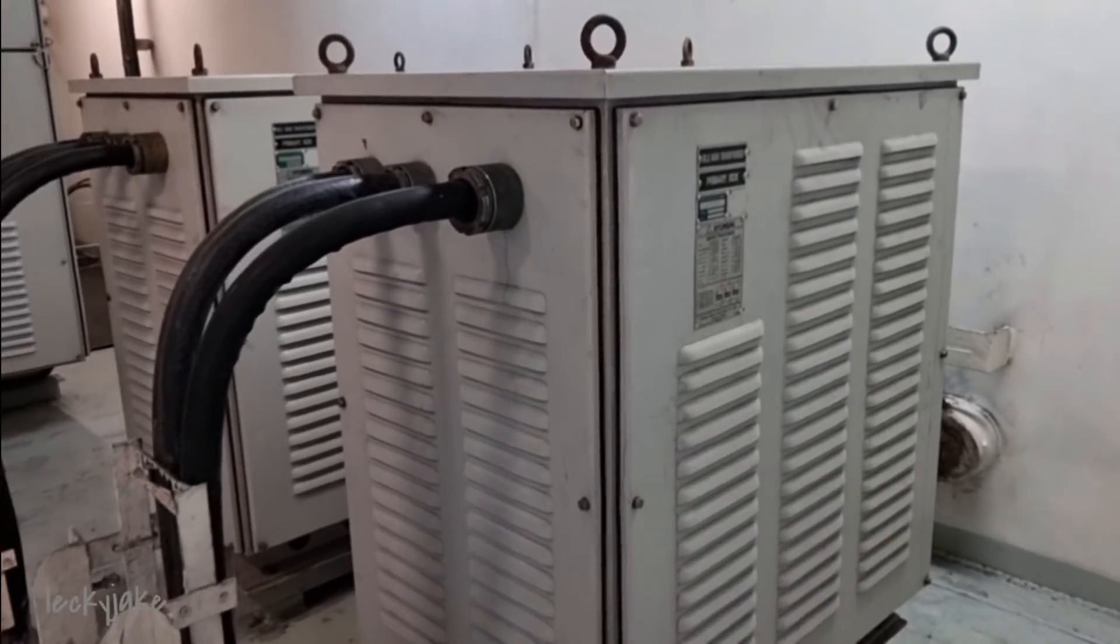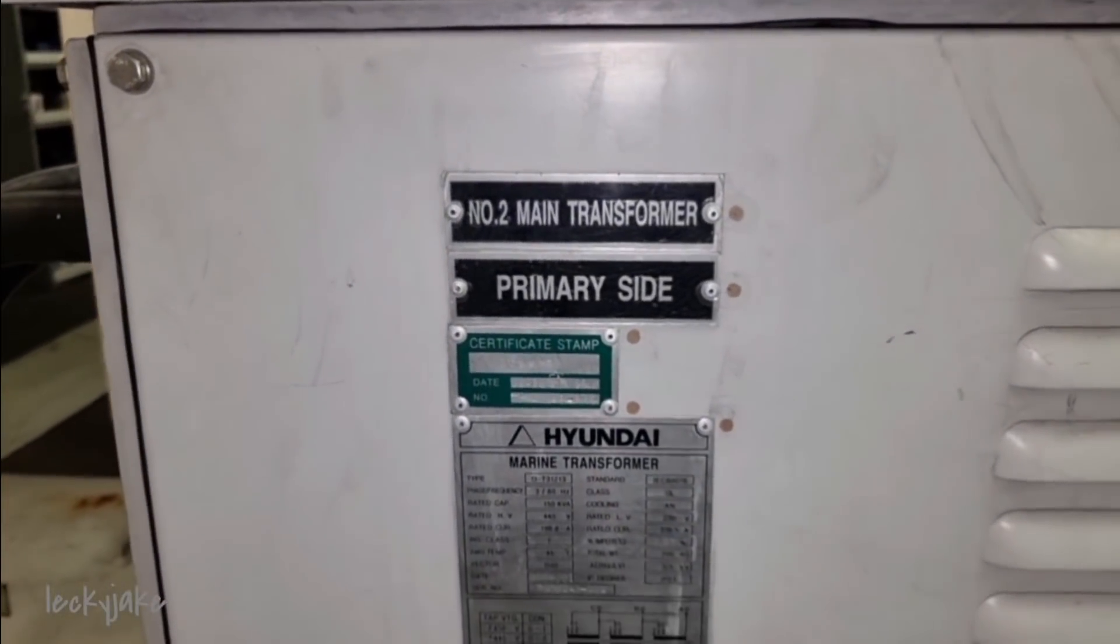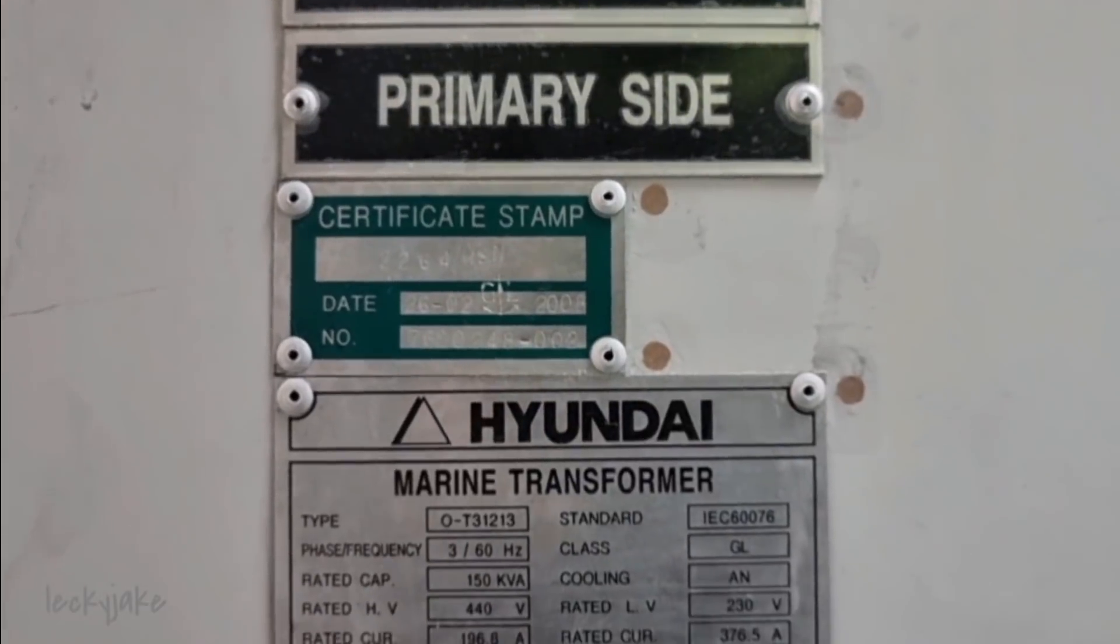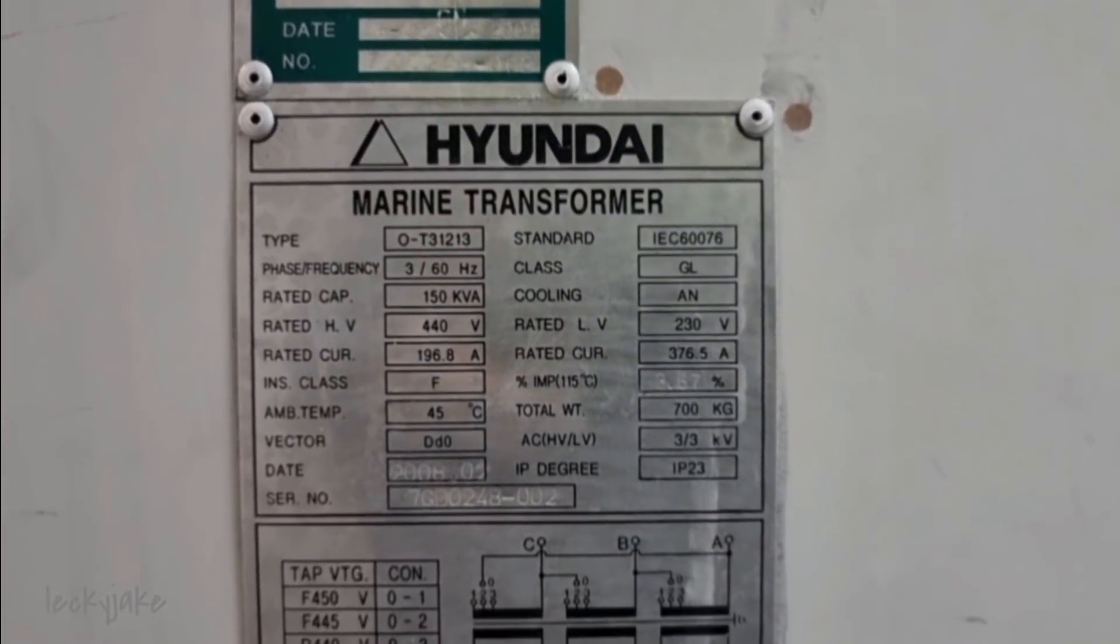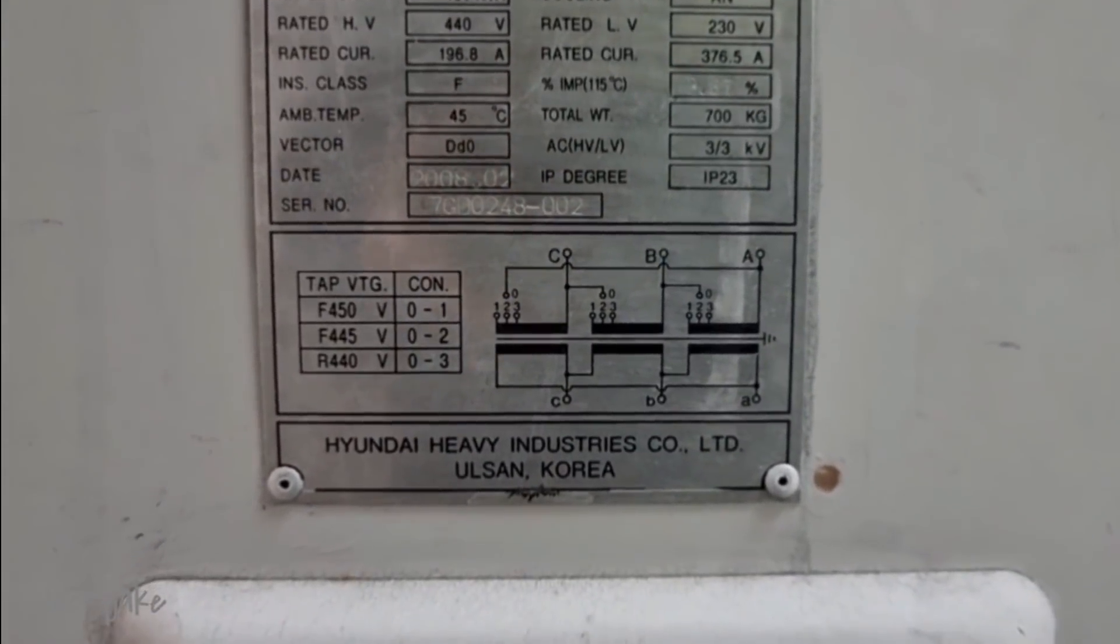So from 440 volts, it is transformed down to 230 volts via two 440 to 230 volts, 150 kilo volts ampere transformers. This is to supply the main switchboard 230 volts feeder section.